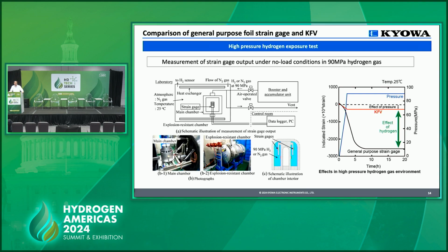The red value here is the KFV strain gauges. The drifting range is within 250 micrometer per meter strain over 20 hours. On the other hand, general purpose strain gauges show a more significant amount of drifting over 20 hours, which is due to the effect of hydrogen embrittlement in the sensing portion.